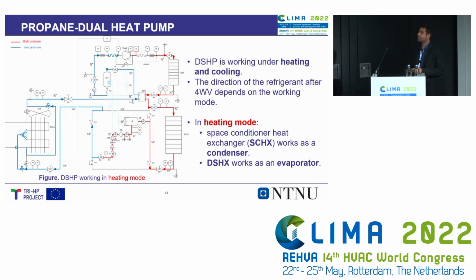The last prototype which we developed is the concept for the propane, but this time with the dual source heat exchanger. I do believe my colleagues explained the concept of the dual source heat exchanger. However, the system is able to work under the cooling mode and heating mode. Here we have the schematic for the heating mode. Again, the high temperature, high pressure refrigerant getting out of the compressor passes through the desuperheater, which we can use for production of hot water, goes through the four-way valve, and from here the system operates depending on the demand.